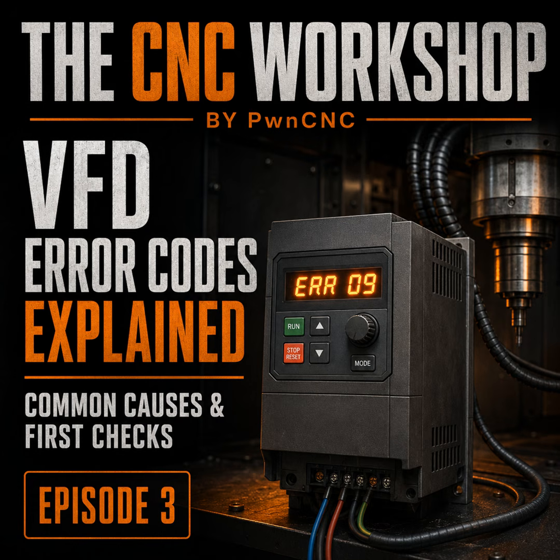Fifth example, no error code, but the spindle starts from the VFD keypad and not from G-code. Investigate controller configuration, control cable, VFD control mode, and the G-code command. That sounds more like a control path problem than a failed spindle motor. I think the pattern is clear now. The code matters, but the most useful question is, what was happening at the exact moment the code appeared?